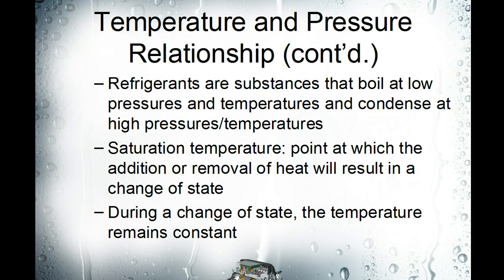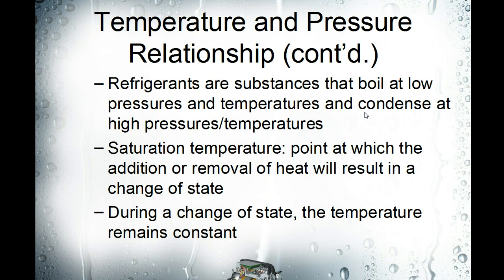Now refrigerants do the same thing as water. They will change state from liquid to vapor and change state back from vapor to liquid depending on the heat that's added or removed. Refrigerants were designed to boil at lower pressures and temperatures. Remember, boiling is change of state from liquid to vapor, and condensing means it will change state back from vapor to liquid at higher pressures and temperatures. And each refrigerant is different.